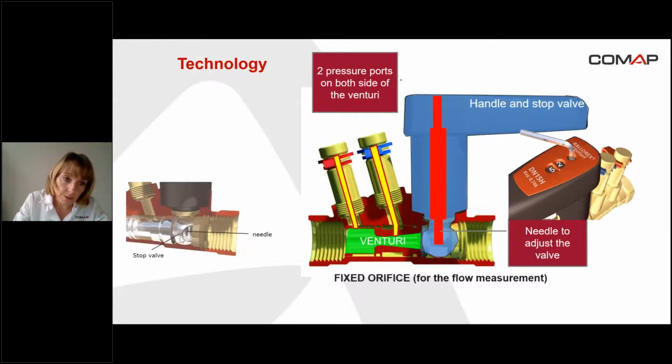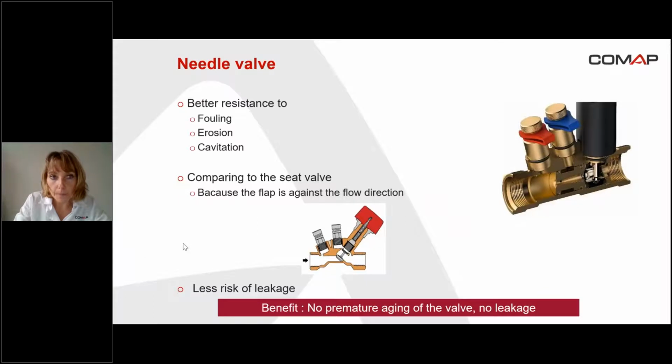Another view here, you can see the cut of the valve with the needle inside and the stop valve here with the ball. So it's a needle valve. What does that mean? That means we have a better resistance to fouling, erosion, and cavitation.